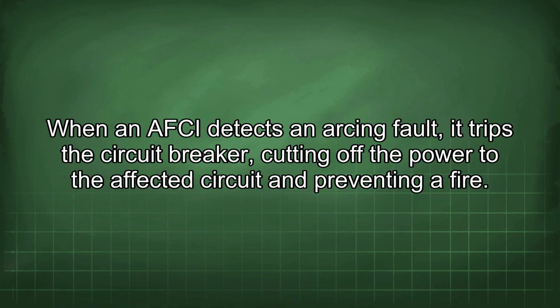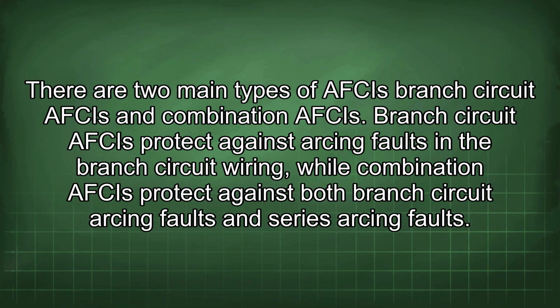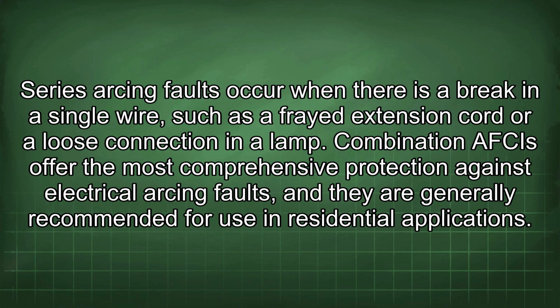and preventing a fire. There are two main types of AFCIs: branch circuit AFCIs and combination AFCIs. Branch circuit AFCIs protect against arcing faults in the branch circuit wiring, while combination AFCIs protect against both branch circuit arcing faults and series arcing faults. Series arcing faults occur when there is a break in a single wire, such as a frayed extension cord or a loose connection in a lamp. Combination AFCIs offer the most comprehensive protection against electrical arcing faults, and they are generally recommended for use in residential applications.